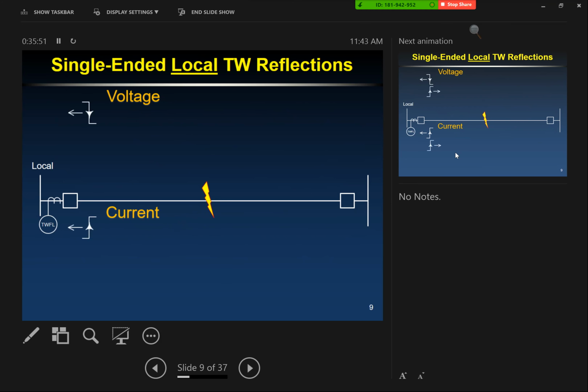So those are traveling back to the local terminal. Now what happens? They meet this junction point, right? And this is going to be a substation with multiple lines or a transformer off of this. What does that characteristic impedance look like compared to the line? Is it higher or lower than the line?